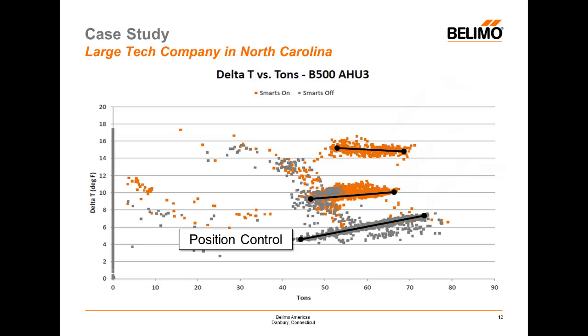The required loads were between 45 and 75 tons, and with position control mode in place, they were achieving Delta-Ts anywhere between 5 and 7 degrees Fahrenheit. On the subsequent time span, with the same valve on the same air handler, the energy valve was switched to flow control mode — a pressure-independent mode where each value of the control signal delivers a specific GPM of water to the coil. In similar load ranges, they were now achieving Delta-Ts in the neighborhood of 10 degrees Fahrenheit.